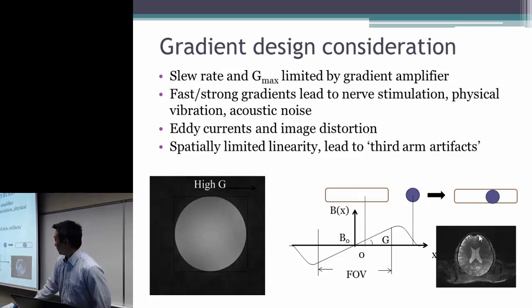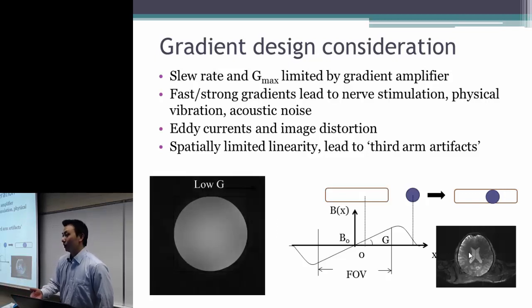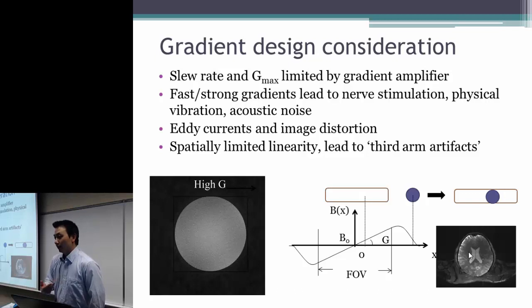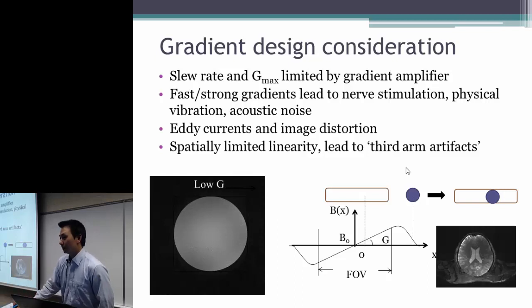So even though I was imaging the brain, I also excited the signal in the shoulder. And the signal excited at the shoulder sees the same frequency due to this decay of the gradient. So we can see that the shoulder now is overlapping with the brain.